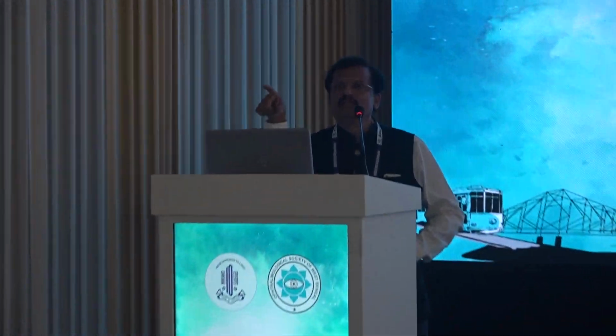That is very important before starting C3R on a patient. So every time you start the machine, calibrate it. Every session you have to calibrate the C3R machine, because most of us use Indian machines, and I'm sorry to say that sometimes they deliver more energy, sometimes less. So you have to calibrate.